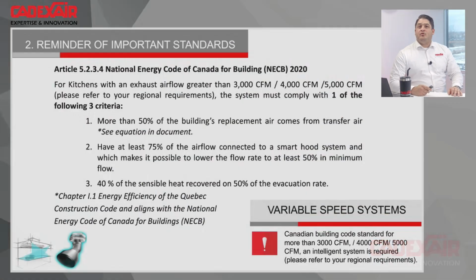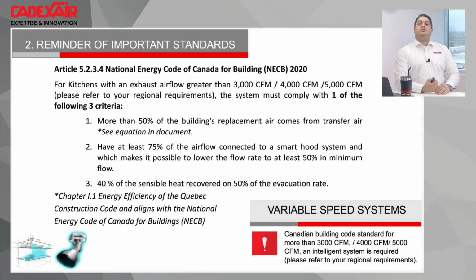After that, okay, there are also some new rules about the energy efficiency code in the Canadian building code. I will say this is a little more difficult when you do this across Canada, because it depends on the airflow generated by the kitchen exhaust hood. As soon as you get more airflow than 3,000, 4,000, or 5,000 CFM, and I will explain why there are multiple values, you will need to have a demand control system.